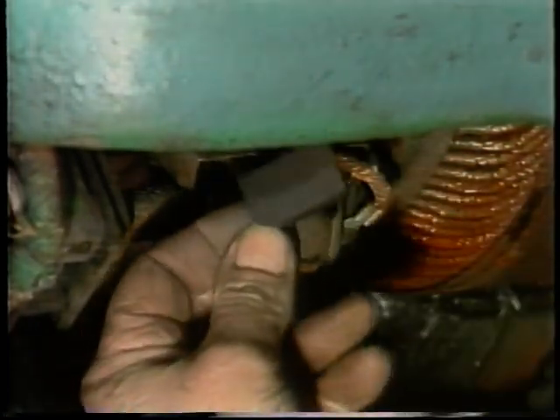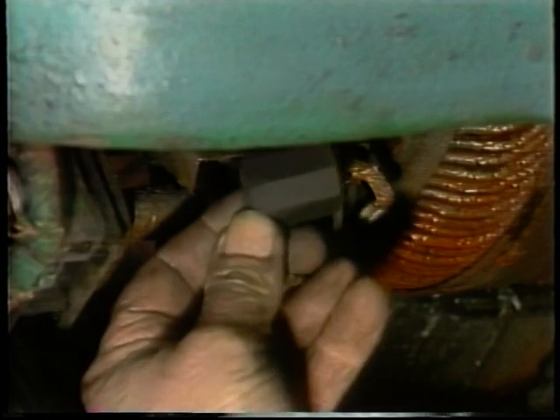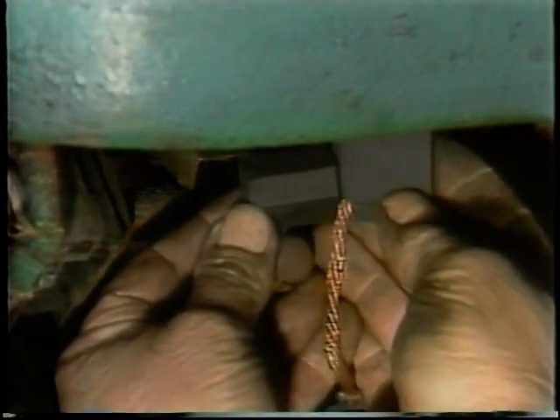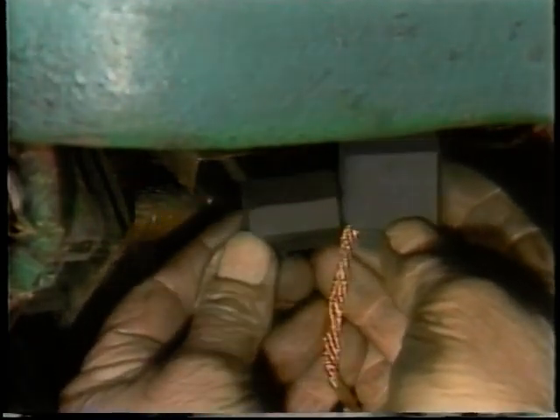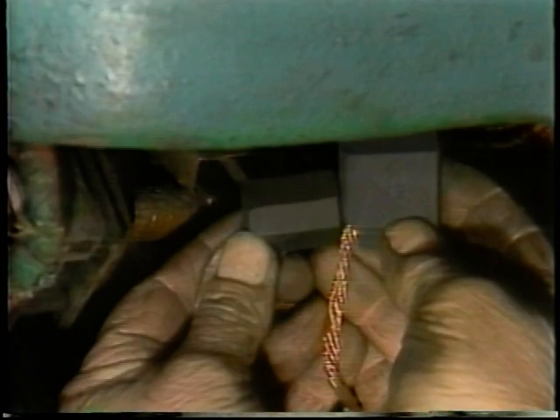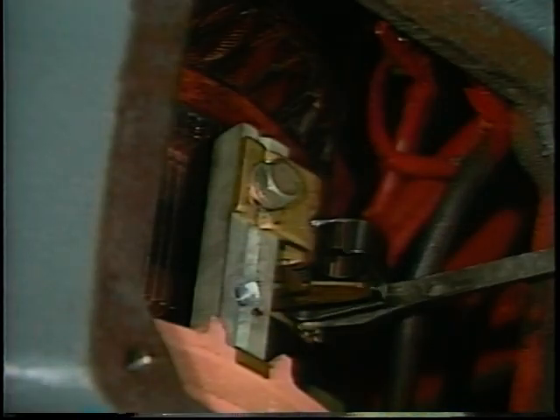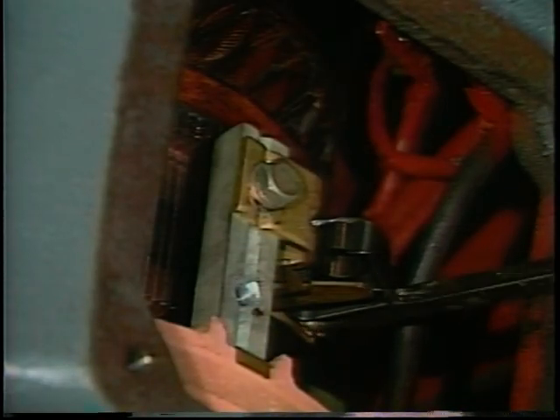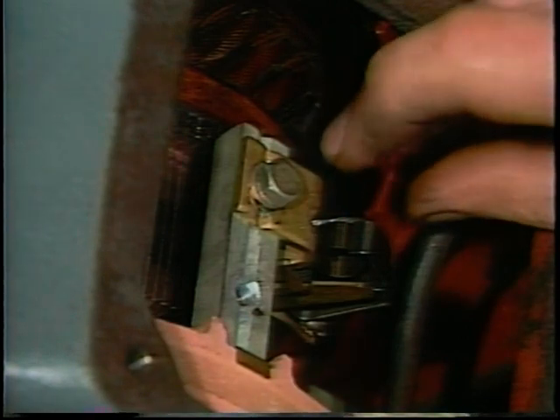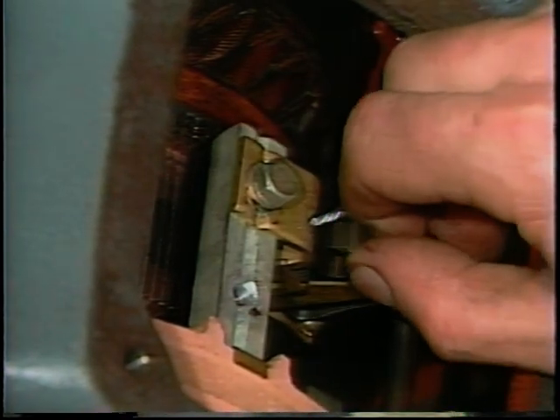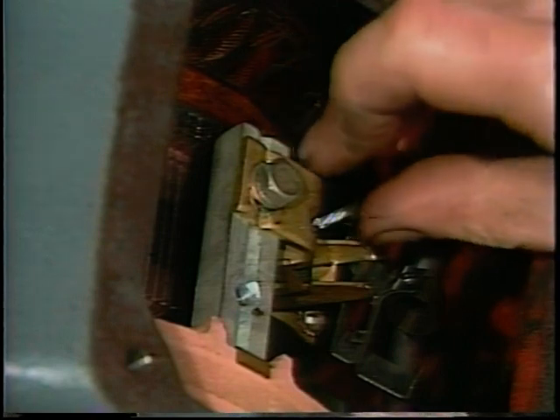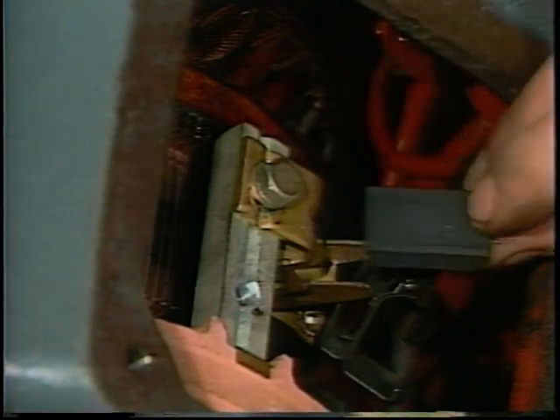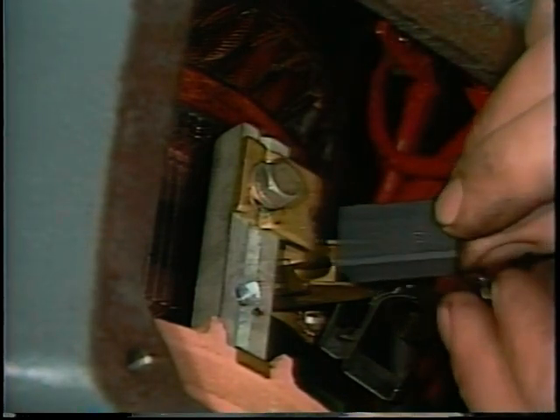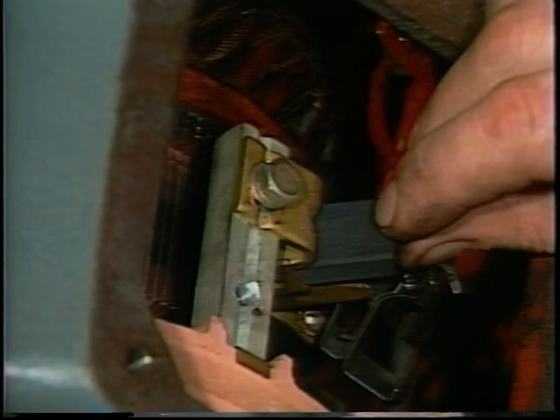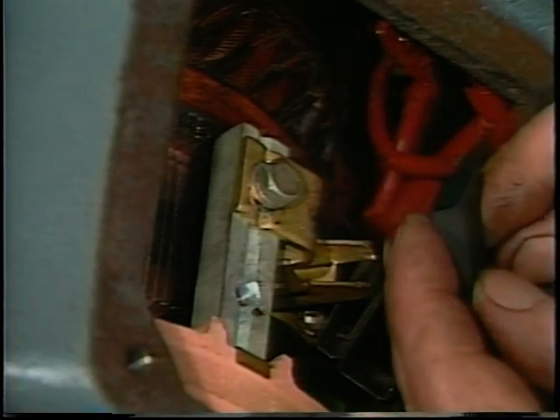Often you have to remove them to check their length. As a general rule, all brushes in a motor should be at least half as long as a new brush. If no brush in the motor is worn down enough to need replacing, be sure to put each brush back exactly as it was in the same brush holder and not turned end for end. They have worn into the shape of the commutator and may not contact the commutator as well in another position.